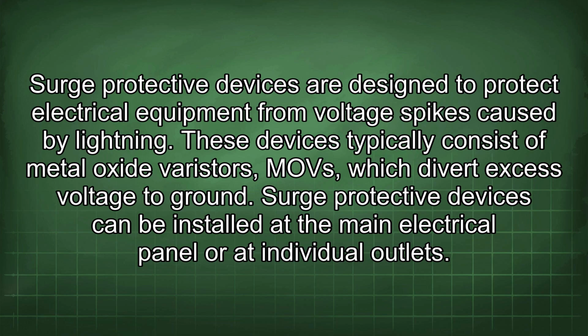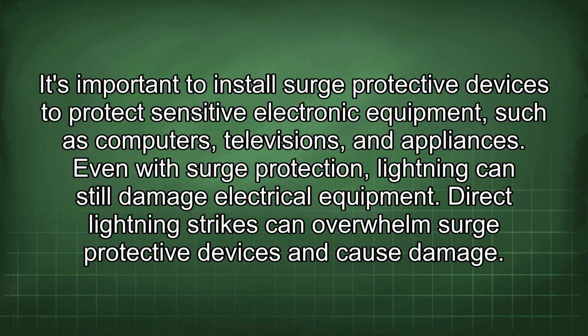Surge protective devices can be installed at the main electrical panel or at individual outlets. It's important to install surge protective devices to protect sensitive electronic equipment such as computers, televisions, and appliances. Even with surge protection, lightning can still damage electrical equipment. Direct lightning strikes can overwhelm surge protective devices and cause damage.